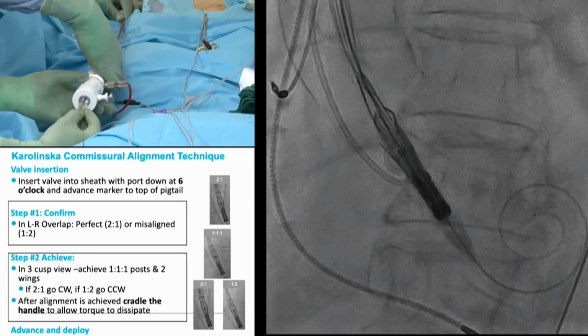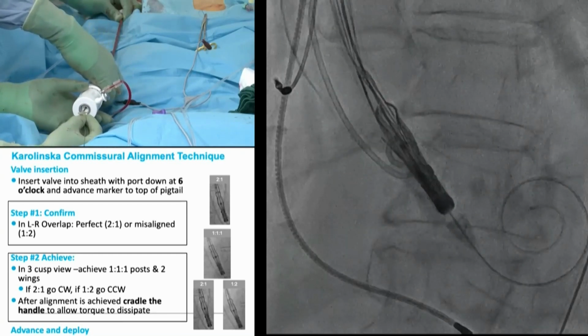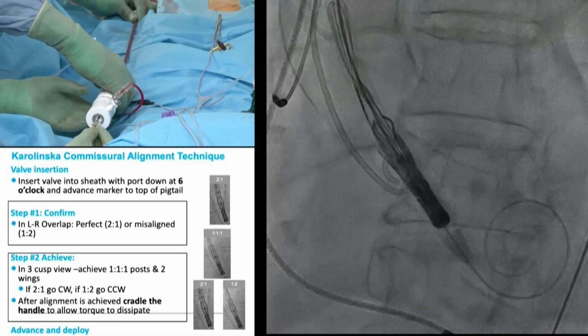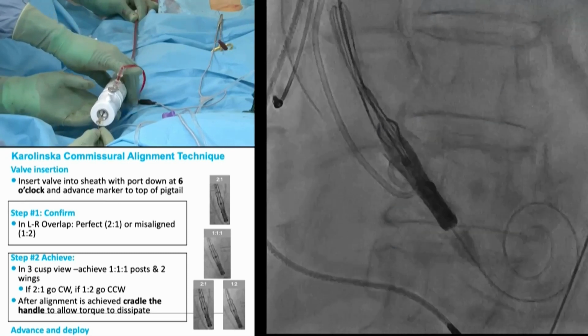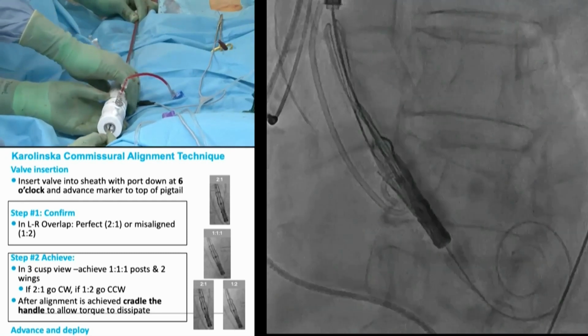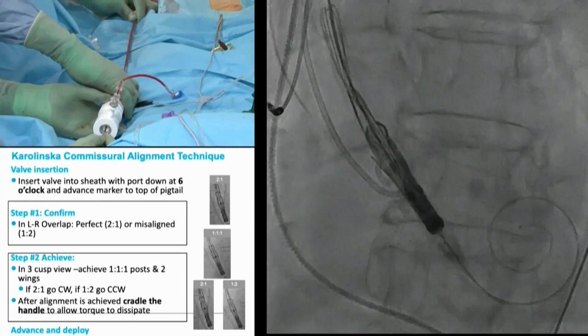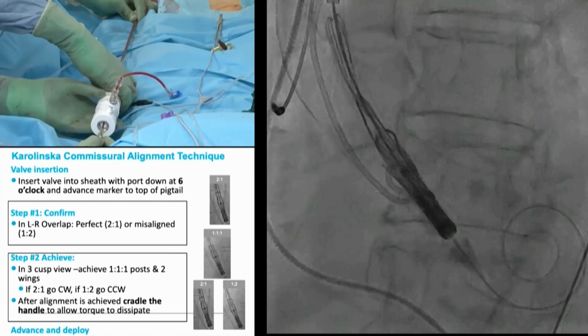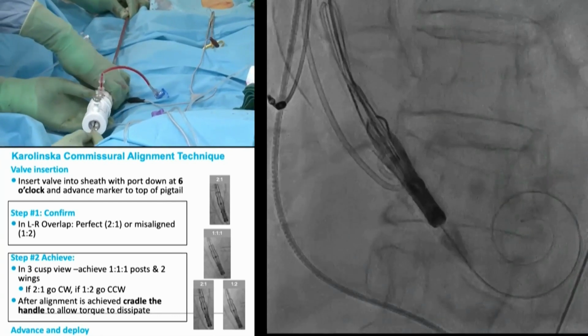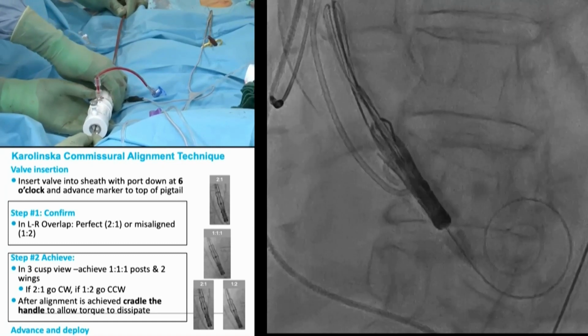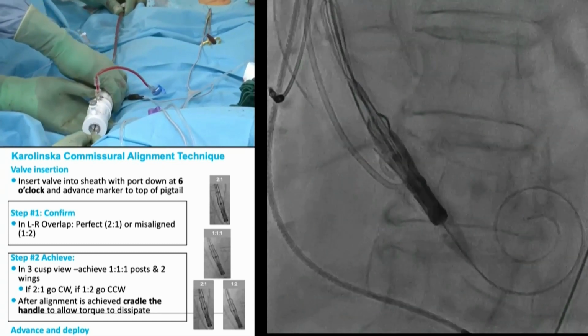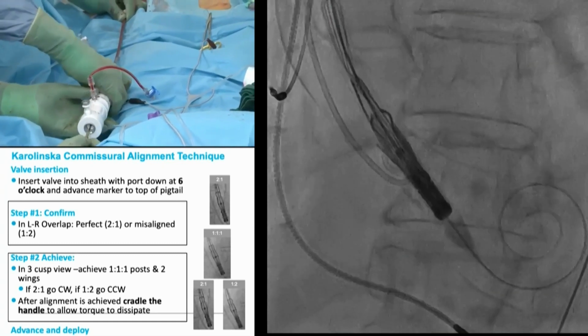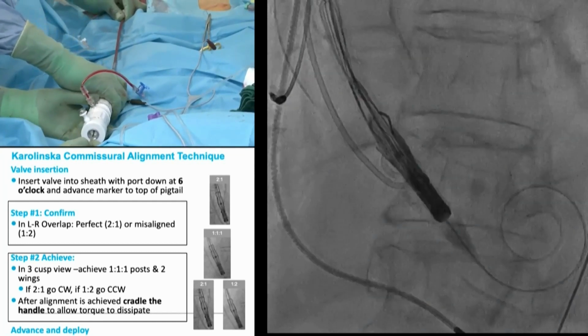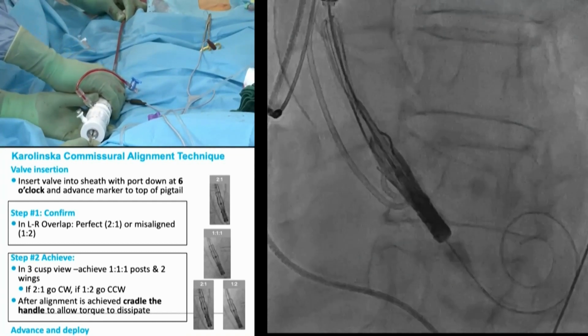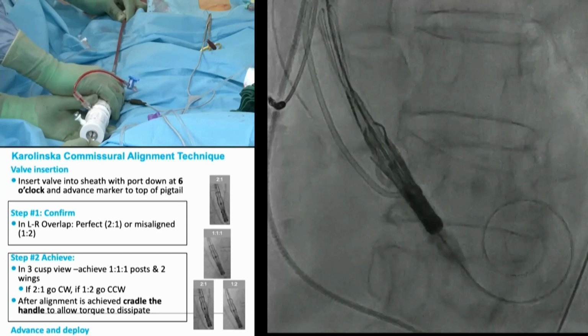Less than a 30-degree turn will actually happen to achieve this, so it's very small changing there. If you could put the hands on the sheath. So now I have turned 180 degrees at the handle, and we don't expect any movement at the annular level until I turn a little more. So at about 3/4 turn at the handle, that will have translated to the annular level, to the tip of the catheter. So I'm going slowly, so as not to overshoot.